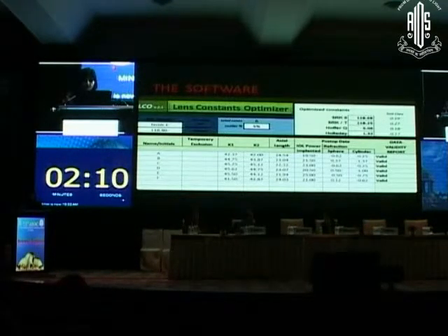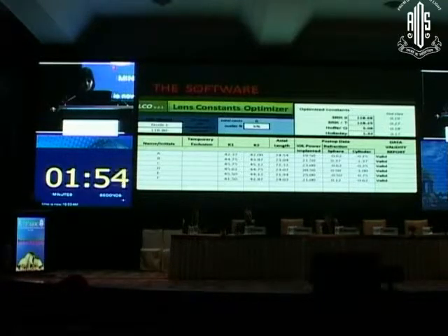After we get the post-op results, we need to feed in the data of the IOL that was implanted, the power of the IOL that was implanted, and the final post-op refraction, the sphere and the cylinder. You would notice that this optimizer has been set for a particular IOL model. You can fill in the IOL model once in the beginning and then keep filling in the data for the others. You don't have to keep repeating it.